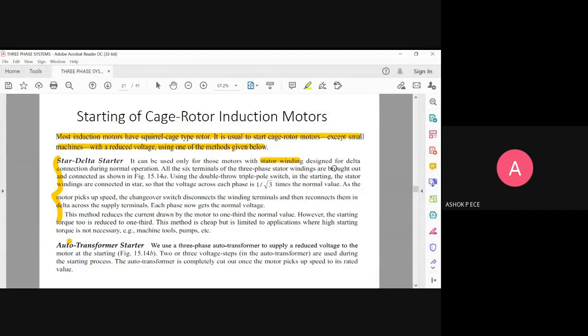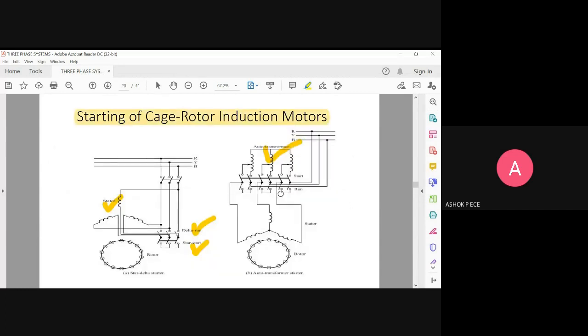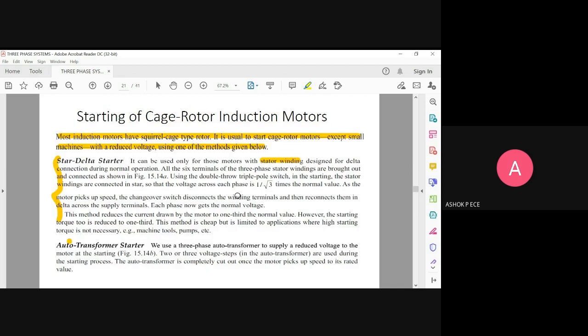All six terminals are brought out and connected as shown in the figure. The stator having delta connection means both ends of each phase (R, Y, B) are connected — so totally six terminals are connected to the delta. Using a double-pole double-throw tri-pole switch, the stator is connected to the star, so the voltage is 1 by root 3 times the normal value.